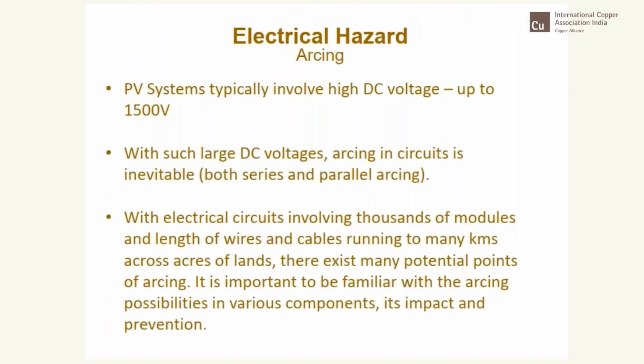Okay. So arcing in PV systems. Typically earlier it was 1000 volts, now we have up to 1500 volts. So with such a large DC voltage, as you know, DC is very difficult. Arcing in a circuit is inevitable, and as was told earlier, in the incident where somebody was trying to remove the fuse box, which was carrying current, the circuit was live, and when you try to break that circuit like that, obviously a huge fire can happen.